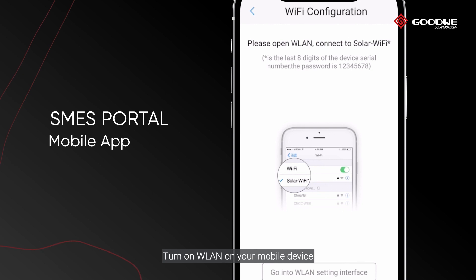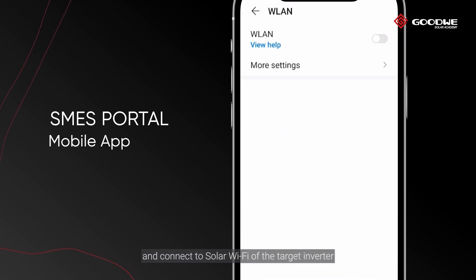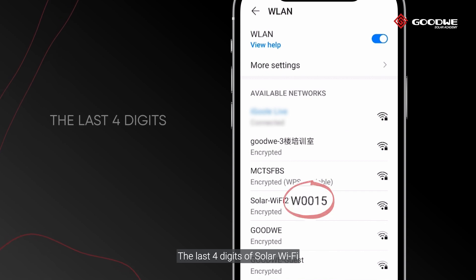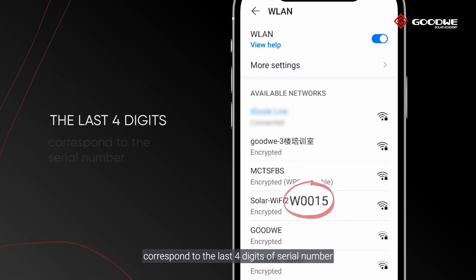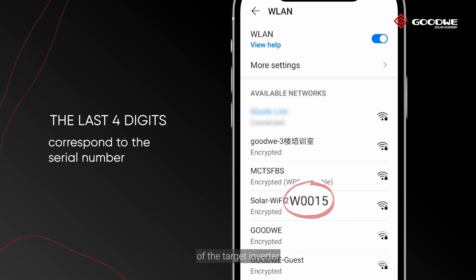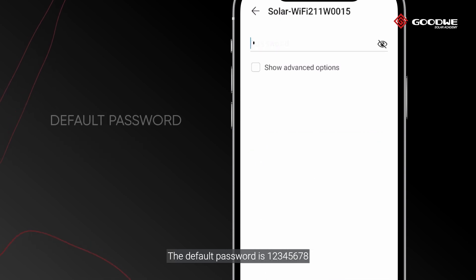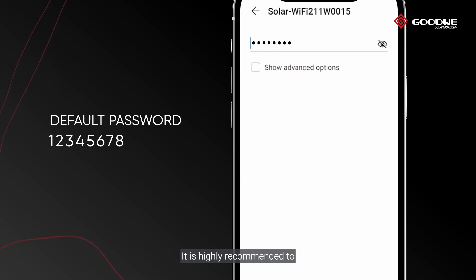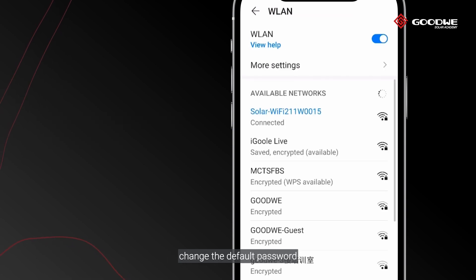Turn on wireless LAN on your mobile device and connect to the Solar Wi-Fi of the target inverter. The last four digits of the Solar Wi-Fi name correspond to the last four digits of the serial number of the target inverter. The default password is 12345678. It is highly recommended to change the default password and keep it safe.